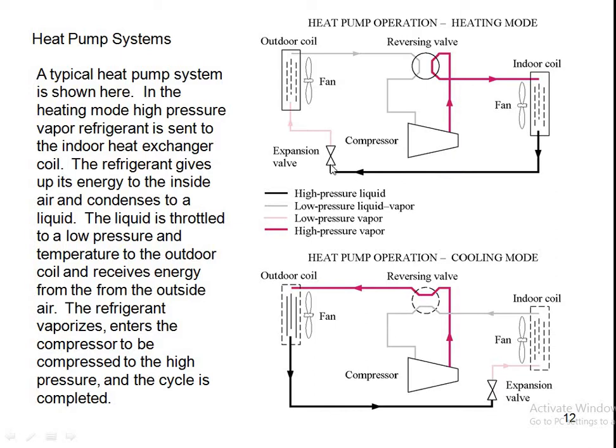Then this liquid goes to the expansion valve and is throttled to a low pressure. Then it goes to the outdoor coil where it receives energy from the outside air, vaporizes, and then goes back to the compressor to be compressed to high pressure vapor again. This is how the heat pump operates — it takes heat from the outdoor coil and rejects it to the inside.